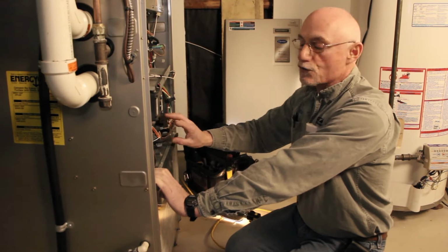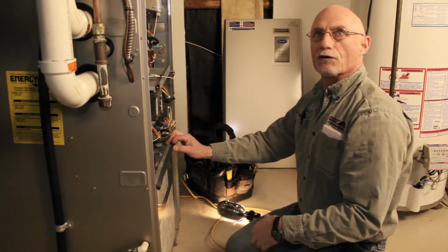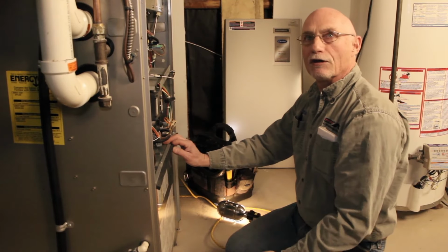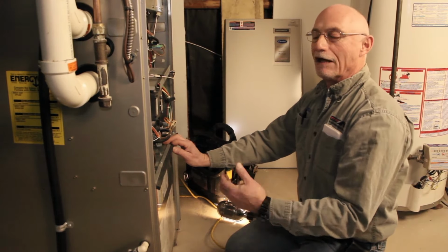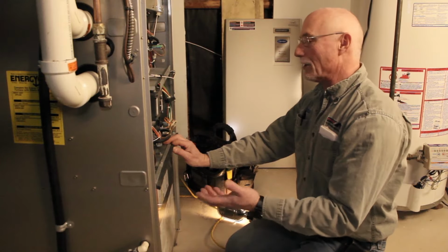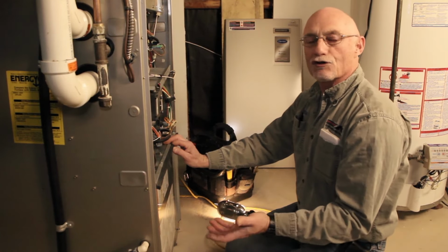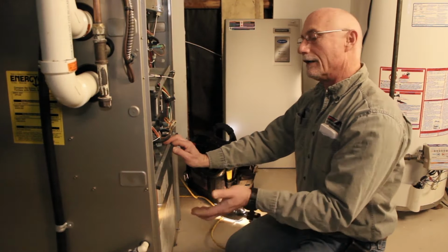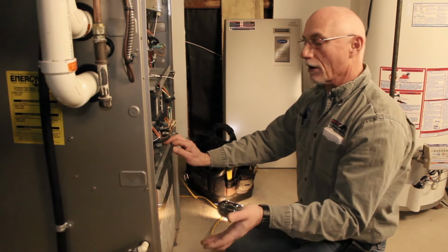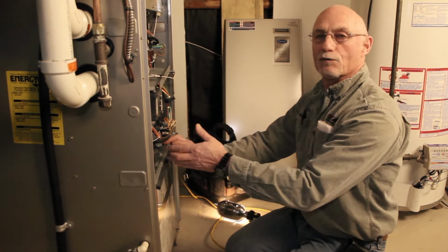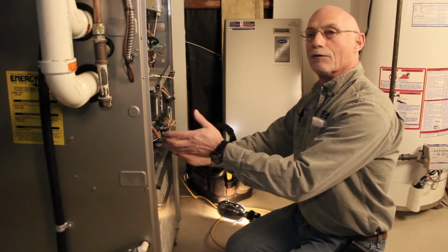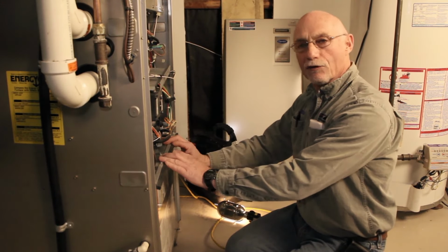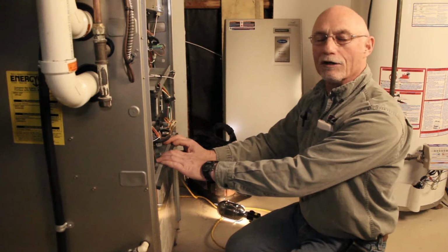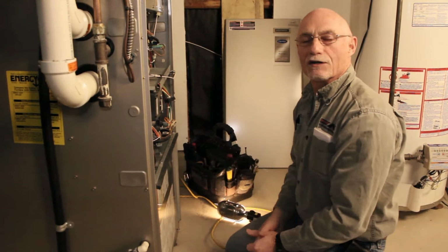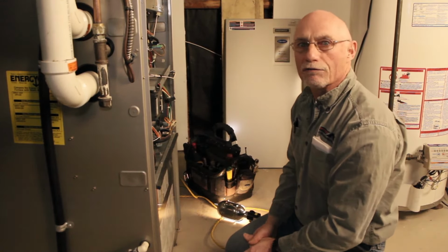We also have pressure switches in the furnace. The pressure switches are linked to the drainage and to the venting part of the system. If the vent pipes got blocked up either by snow or other restrictions, the furnace will not start. If your drain line also gets plugged up because of blocked drain lines, which we've inspected, then the pressure switches again will shut the furnace down to say, hey, there's a problem with it, and it just makes things much safer compared to the older furnaces.